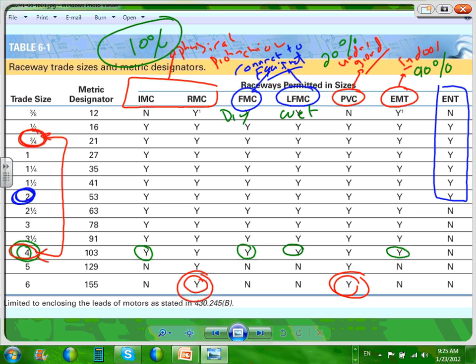Another good application where this becomes an option is if you have a highly corrosive environment. Very highly corrosive. By the way, Phil, every time you have a highly corrosive environment, non-metallic wiring methods become superior. All the time. That's why we underground PVC.